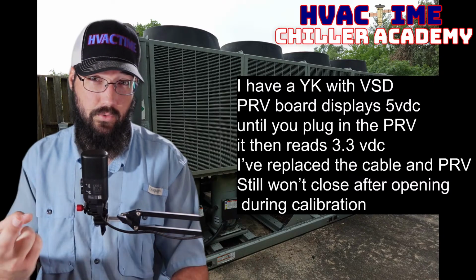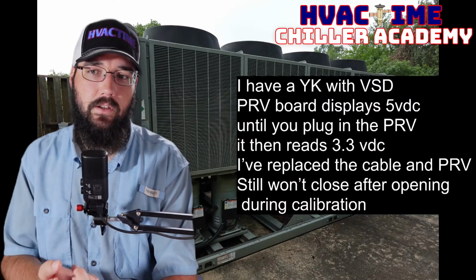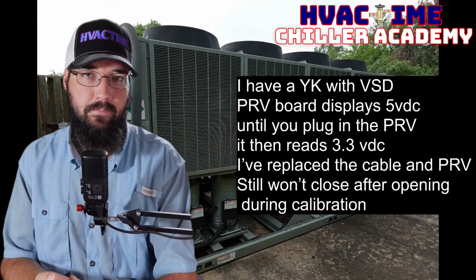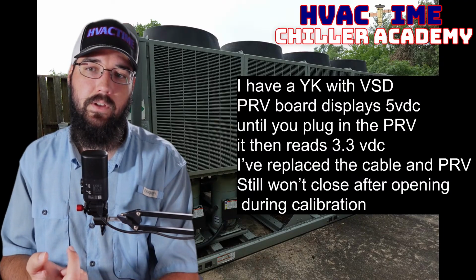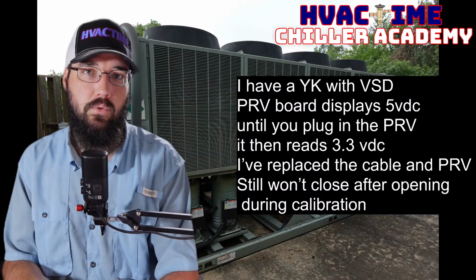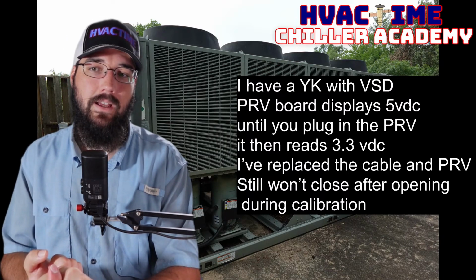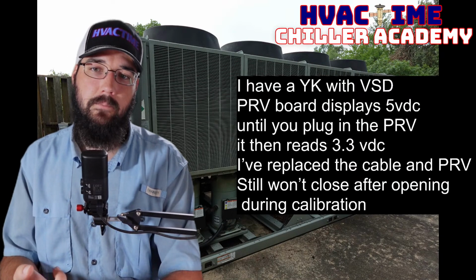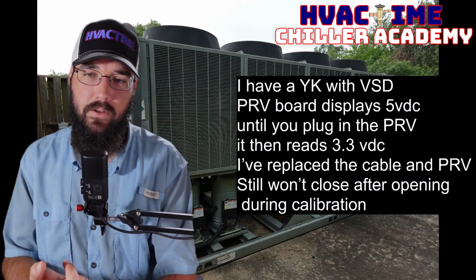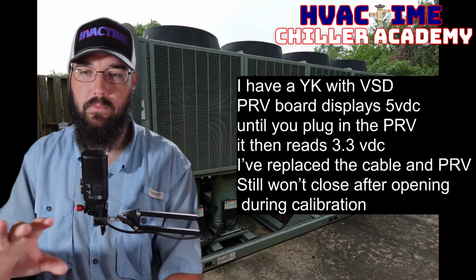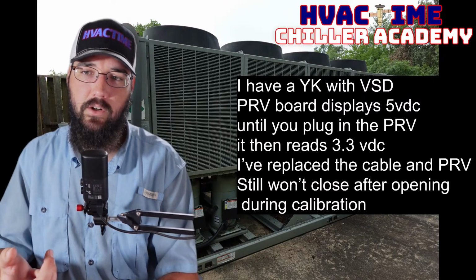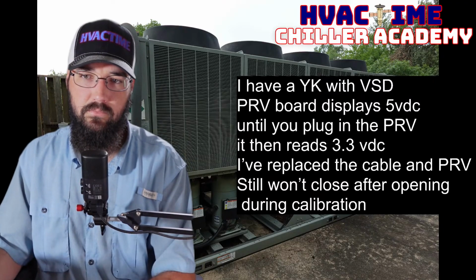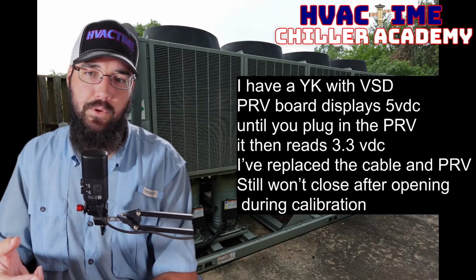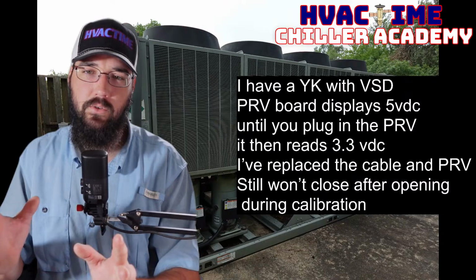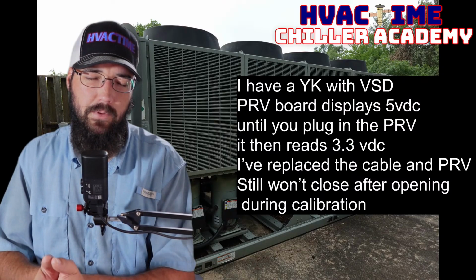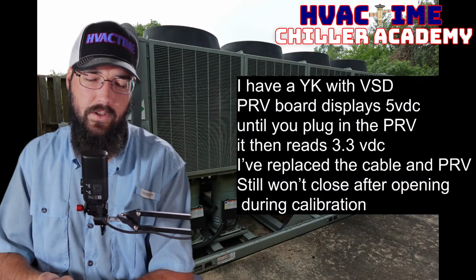My mind goes in two directions. One, the module may be a problem. The PRV goes through the I/O board, so you could have an I/O board problem. He said PRV board, so let me break down some of these acronyms. VSD, variable speed drive, so that's your variable frequency drive. PRV, pre-rotation vane. So, PRV board. The PRV feeds off of the I/O board.